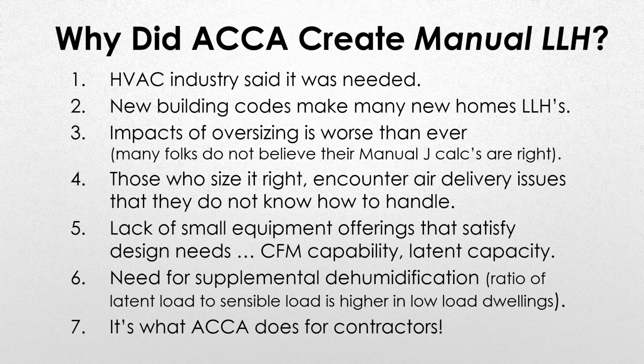So why did ACCA create the manual? Actually, the industry said it was needed. Wrightsoft in particular, we had people starting to come to us saying, hey, we're getting these 2,000, 2,500 square foot homes that only need a ton or a ton and a half of cooling. And our programs don't deal with that really well because of the airflow issues and the associated duct design with that, as well as equipment selection. Because when you have a low load home, it brings up some real equipment issues. We're finding that the new building codes make many new homes low load homes, which is kind of what I said. We're also finding that the impacts of oversizing is worse than ever. And that's largely due because a lot of people don't believe their Manual J calcs are right. So they just do what they did before.